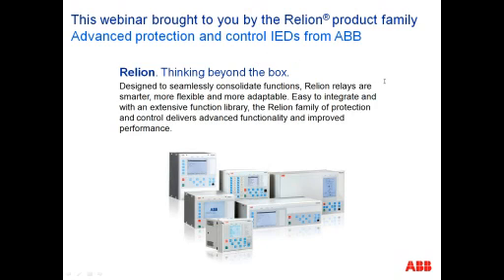Let's see. How are the low impedance and high impedance different in operation? The high impedance is a single element device that you basically, before coming into the relay, sum all the currents, and the requirement is that all CTs have to be the same ratio and of very similar characteristic. You sum all these quantities up, which for a non-faulted condition would of course be 0, and you go through one operating element to operate.